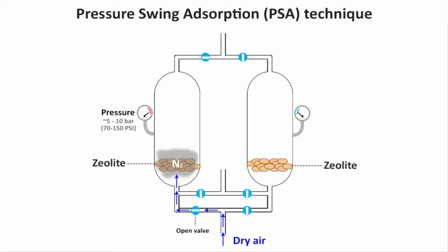Since we don't need nitrogen, the unwanted nitrogen gas is adsorbed by the zeolite during the pressure build-up and settles at the surface of the tank. When the first tank is almost full, the nitrogen absorbed settles down at the bed of the vessel and is then released into the atmosphere — or captured for other purposes — through a valve. When the first tank is full, the pressurized oxygen is collected through an outlet.